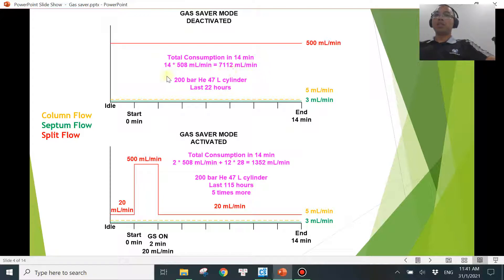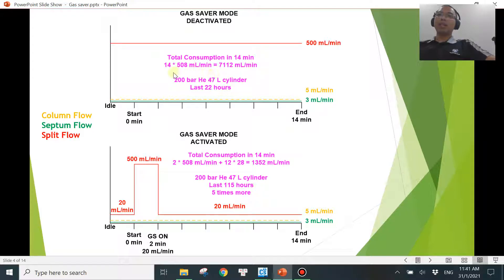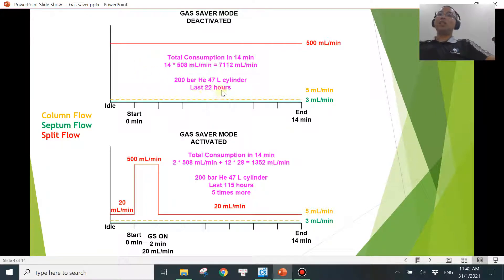If you perform a quick calculation: a typical helium cylinder is filled to about 200 bar and the big cylinder is about 47 liters. At a consumption of 7,000 mL for a 14-minute run at 508 mL/min continuous flow, that cylinder will last you for about 22 hours. Even if you don't run the GC, it's consuming the same flow rate at idle. So one cylinder will last you properly about one day — and you may be spending a couple hundred dollars to buy one cylinder of helium every day. That's why gas saver mode is so important.